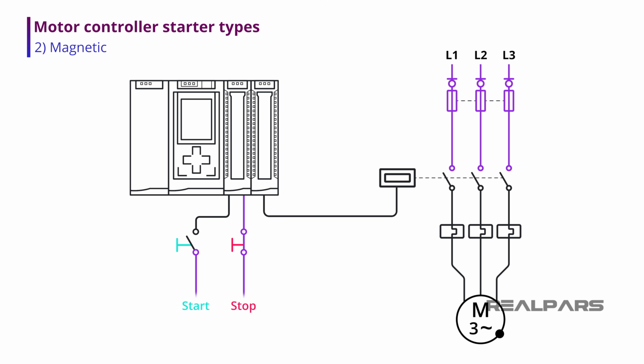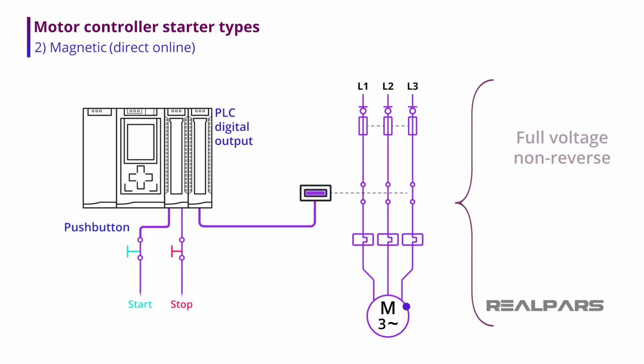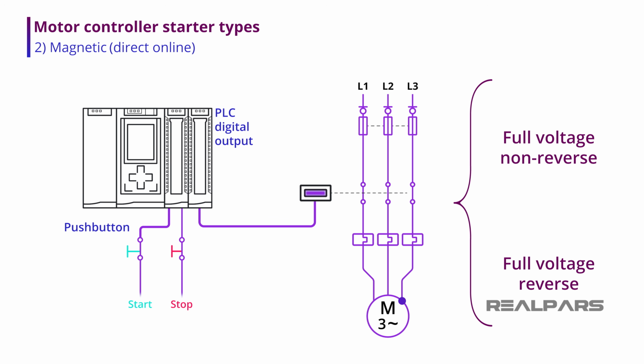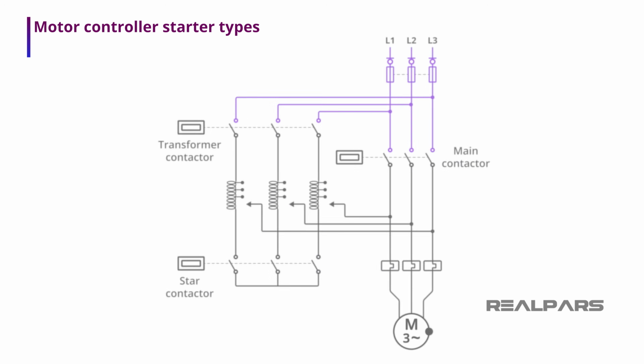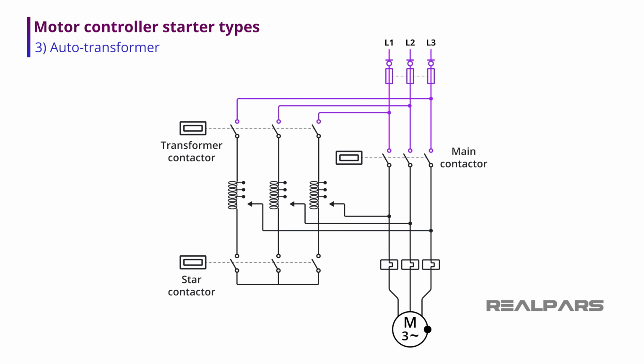Magnetic motor starters, or direct online starters, are the most common single-speed starter type. For magnetic starters, a PLC digital output, a push button, or a selector switch is used to pull in a coil, which magnetically holds the starter contacts closed, allowing current to pass to the motor. Magnetic motor starters are used with FVNR and full-voltage reversible motor controllers. Auto transformer motor starters are commonly used in reduced voltage starting applications, especially with large motors.